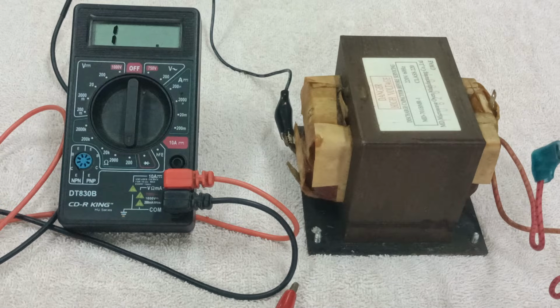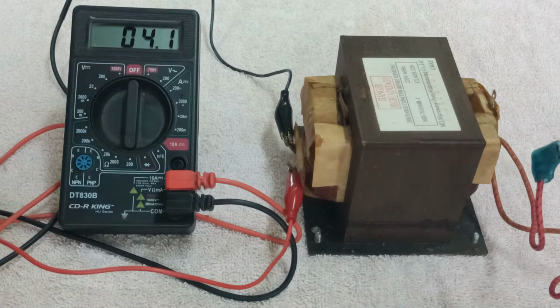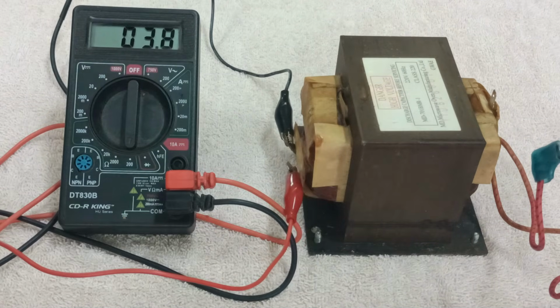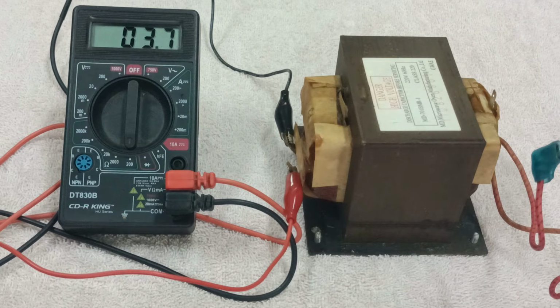Now I am testing the transformer using a digital ohmmeter. First, I test the primary winding. Set the digital ohmmeter range to 200. Then connect the probes to the primary winding terminals. It shows a low resistance of about 4 ohms. This is a good test.